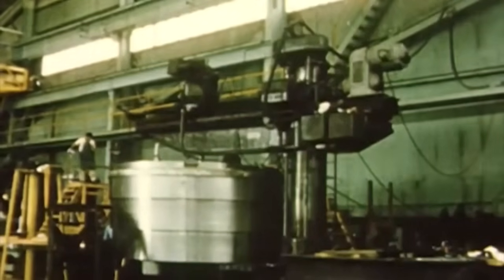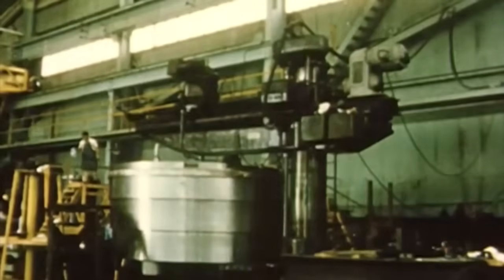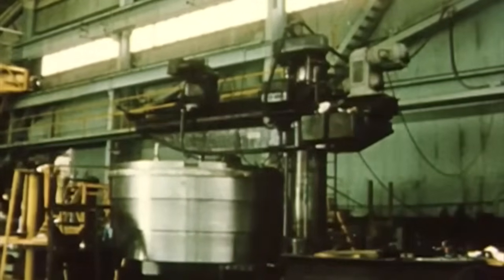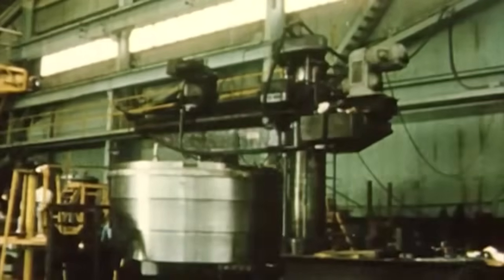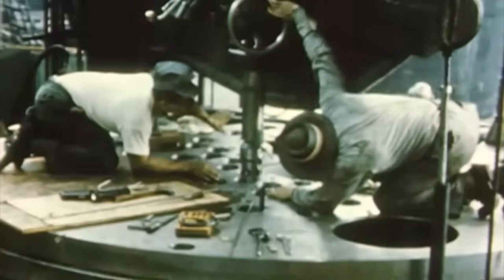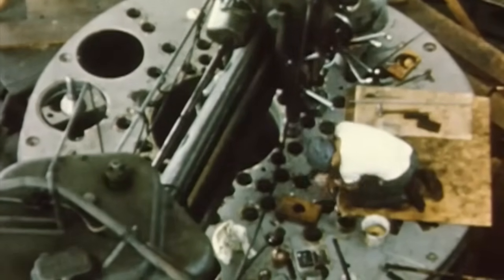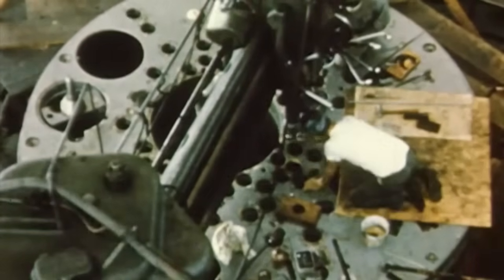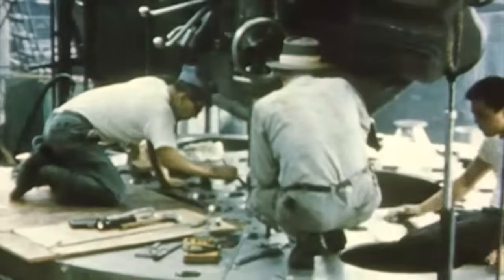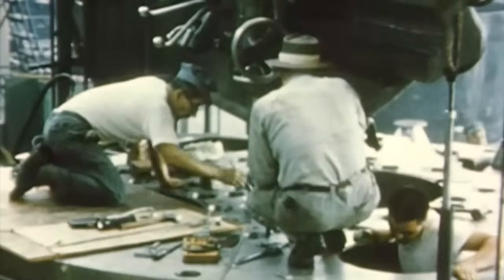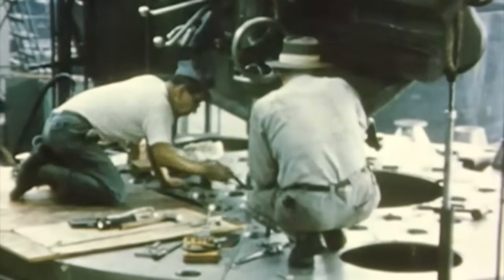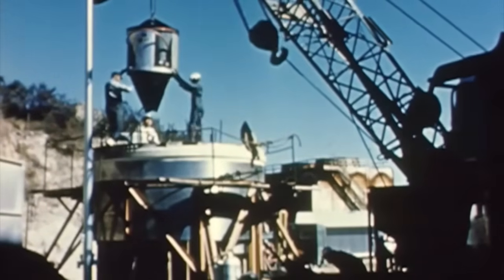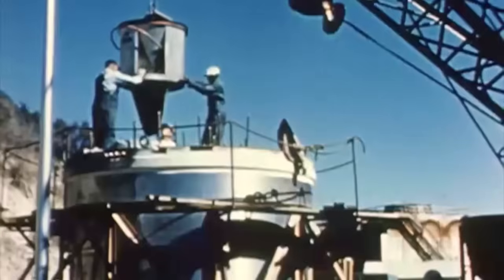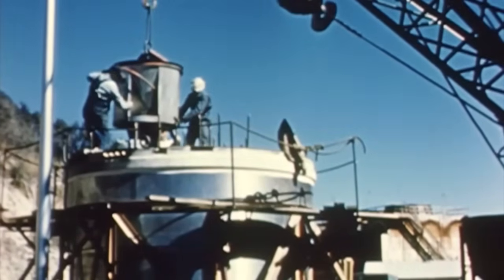The form for the rotatable top plug is made of type 405 stainless steel. It is filled with dense concrete 6 feet in thickness and shields the area directly above the reactor core. There are 81 small plugs and 4 larger plugs extending through this shield. These plugs are located to permit access for removal of any fuel element or moderator assembly within the core tank when the shield is rotated. Total weight with concrete and plugs is 75 tons.